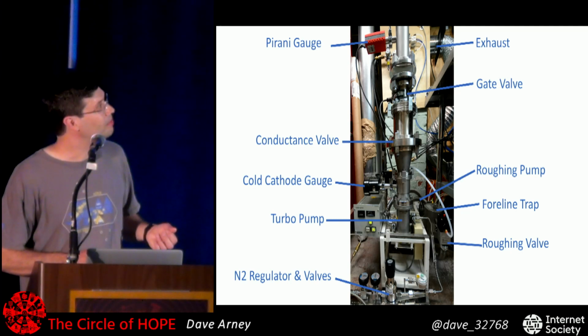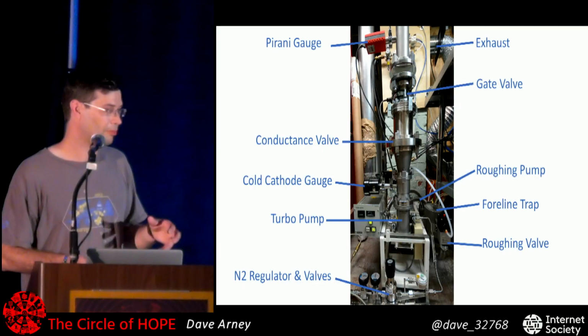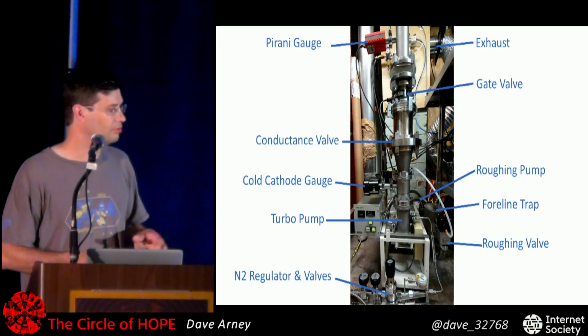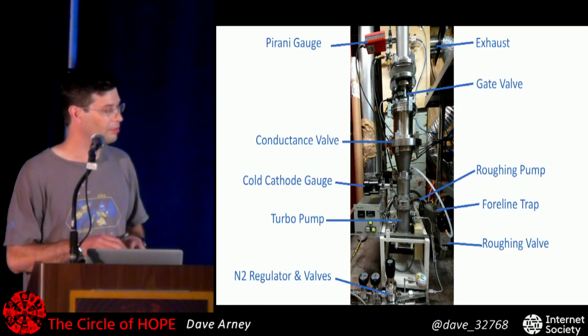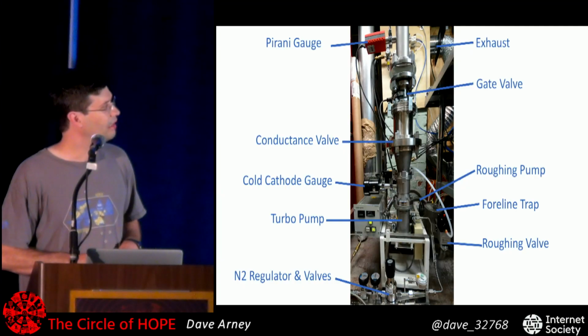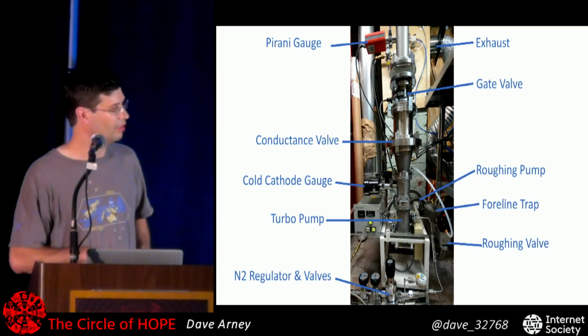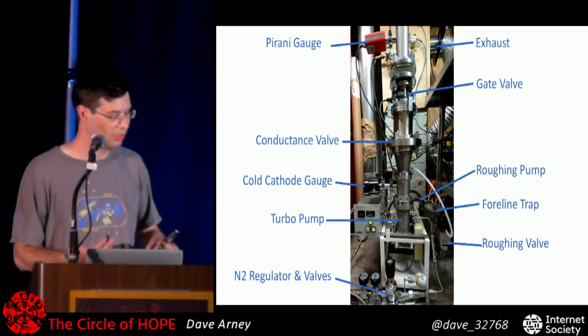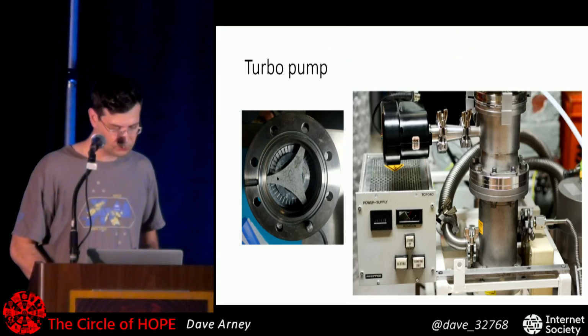The gauge up here above the gate valve is good for measuring higher pressures, down to 10 to the third, 10 to the minus third, 10 to the minus fourth torr. The cold cathode gauge down here is the cheapest gauge I could find that goes much lower, so I can tell how well the turbo pump is actually working.